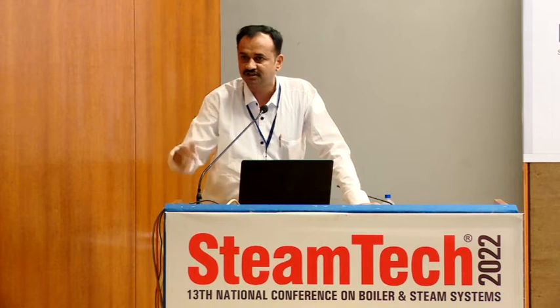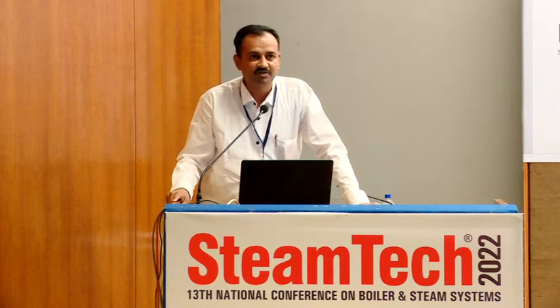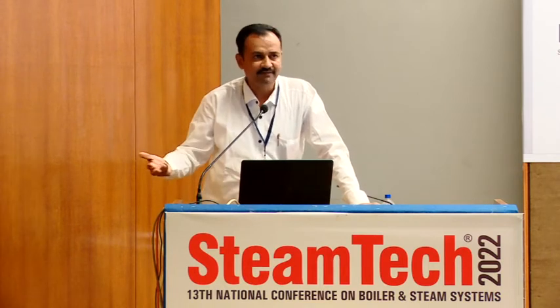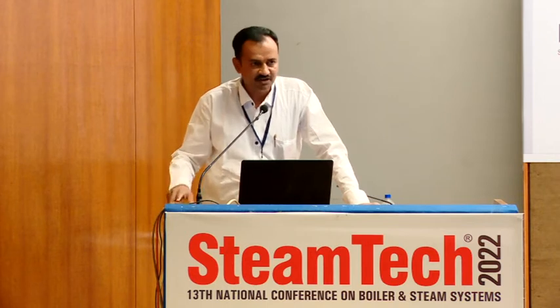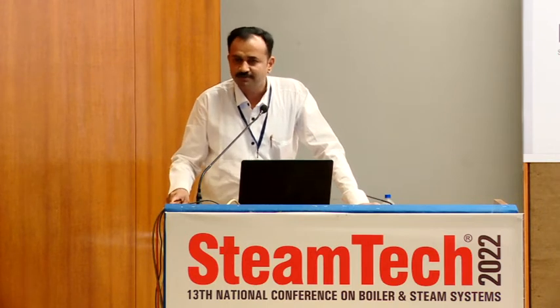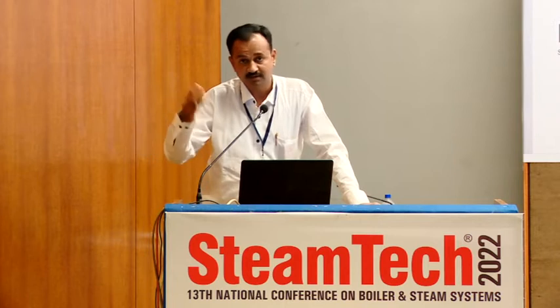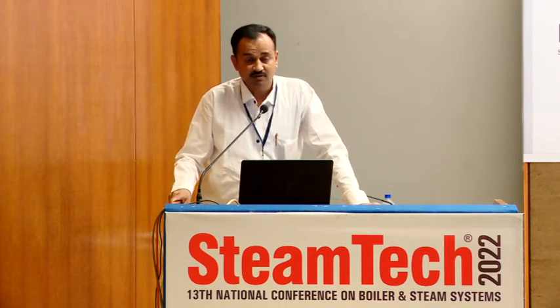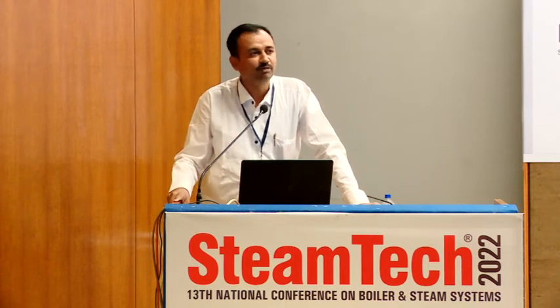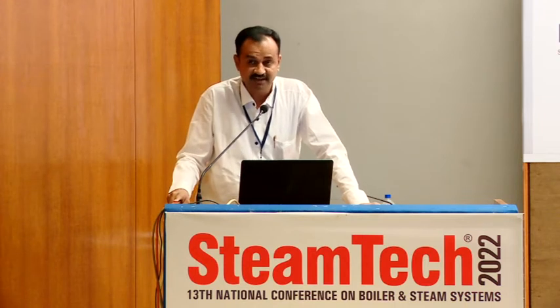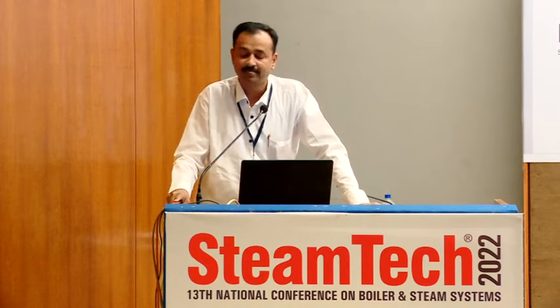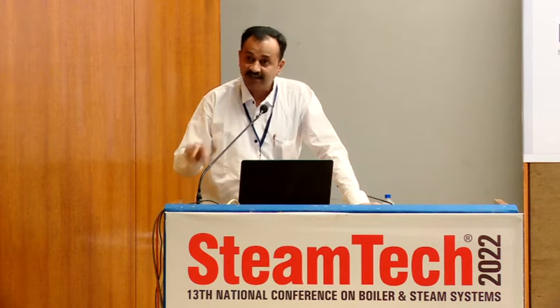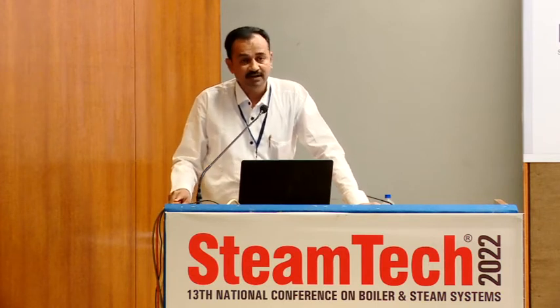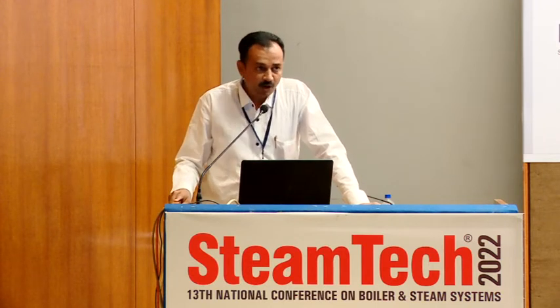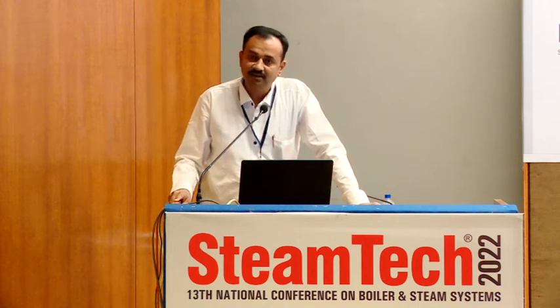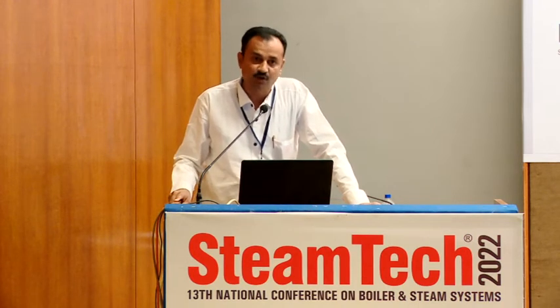And the indirect efficiency is 100 minus the breakup of the losses. These losses are the dry flue gas loss, moisture loss, radiation loss, on-off losses, purge losses, etc. And in addition to these, there will be the blowdown loss. That is not a part of indirect efficiency, but it's a loss. I will not go into the detail, but one thing we need to keep in mind is how we can reduce these losses so that the user can have the best operating steam cost.